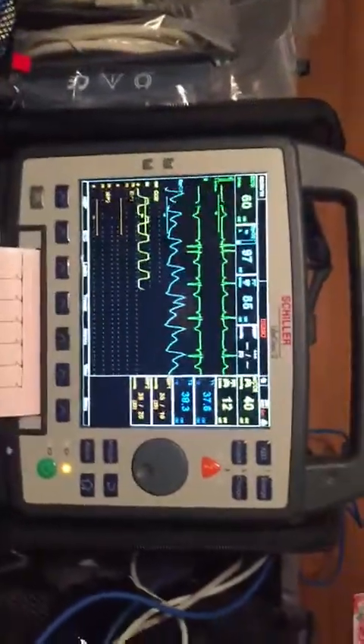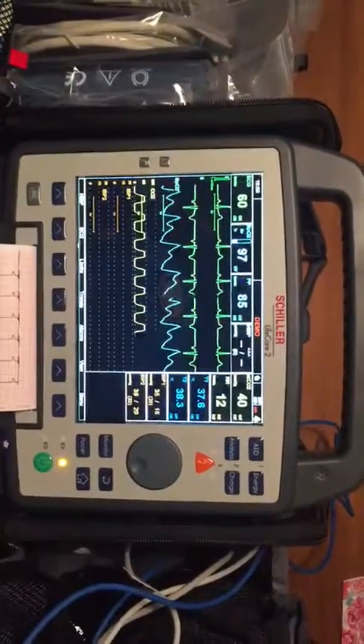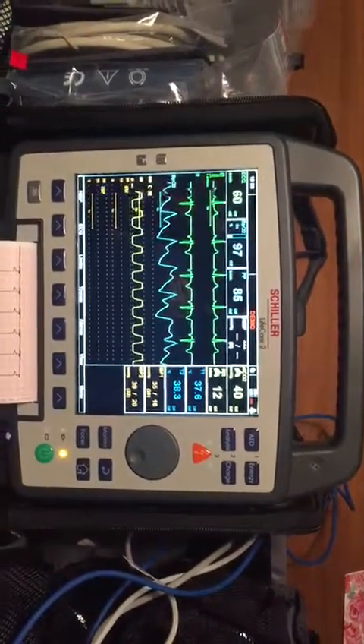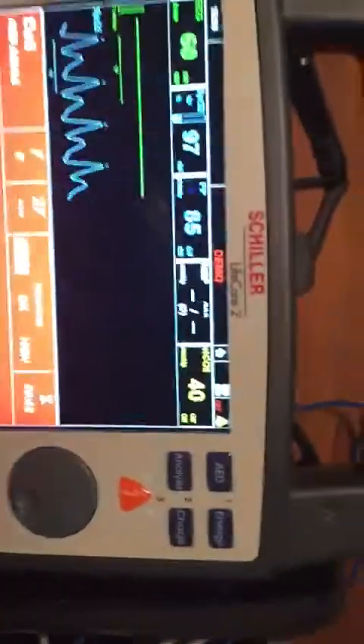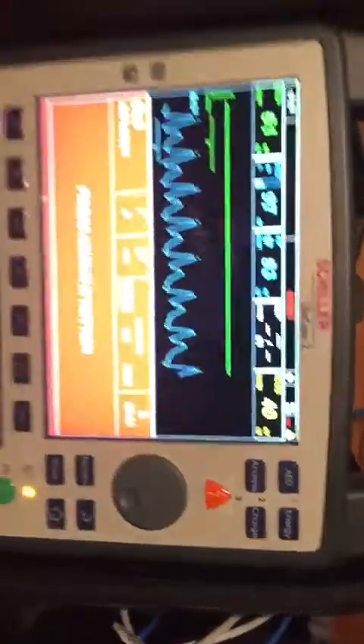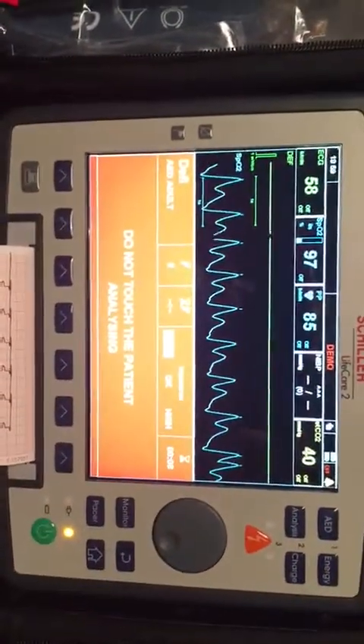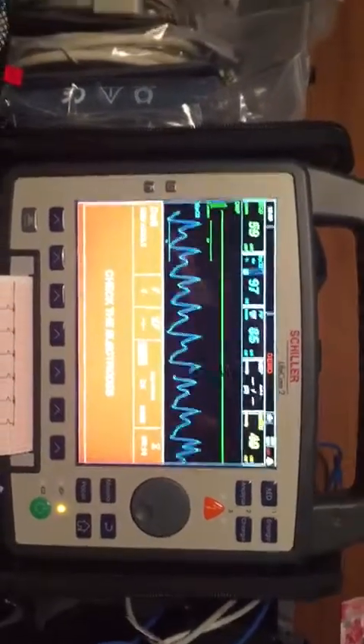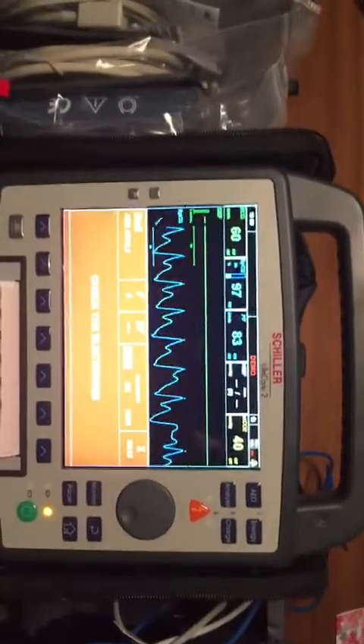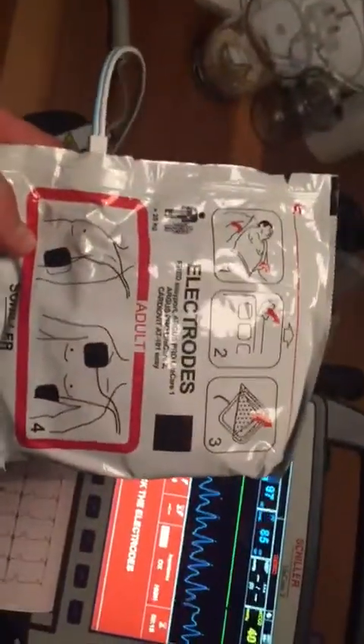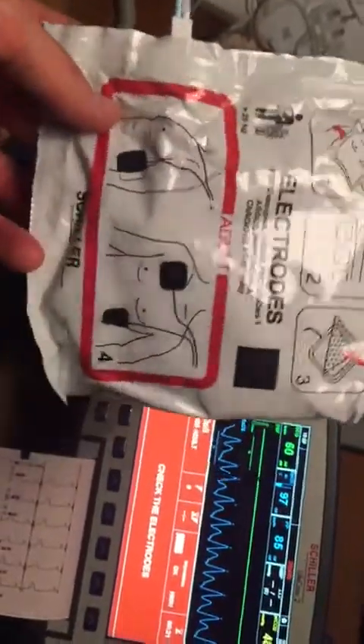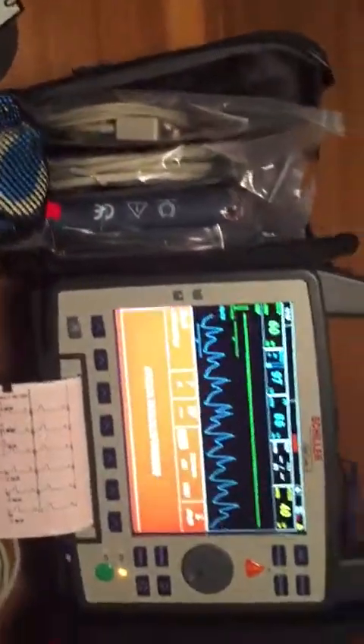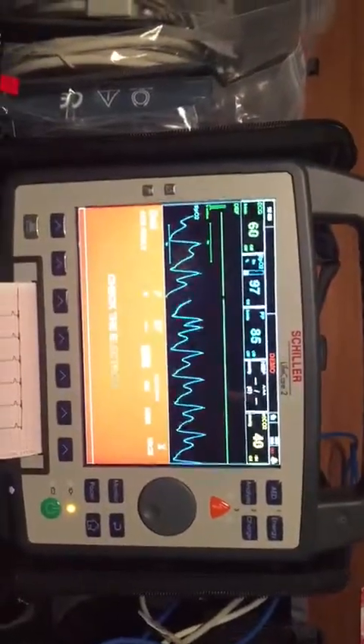Now we enter the defibrillation mode. For the defibrillator we have 2 modes. It's an AED, automatic external defibrillator. Press analysis button. Do not touch the patient. Analyzing. Check the electrodes. Now it's not proceeding, the AED, the defibrillator, because I didn't insert the electrodes. These are the electrodes for the AED. These are pads, which have to be connected accordingly on the chest, on the upper and the below. Check the electrodes.